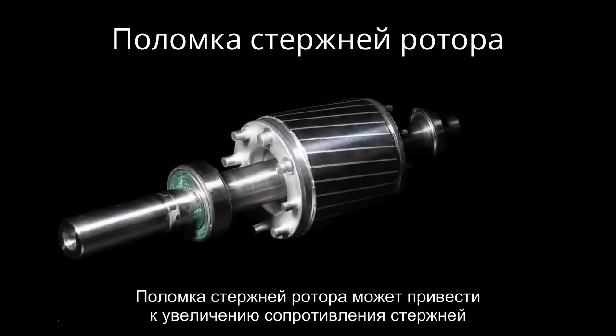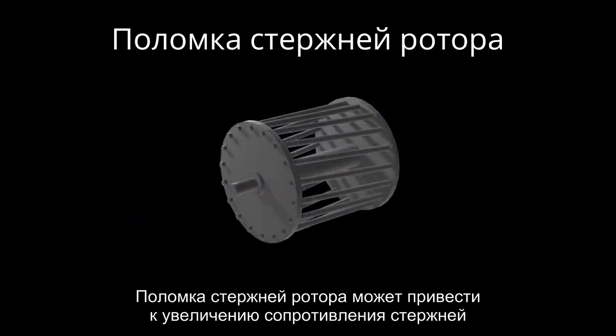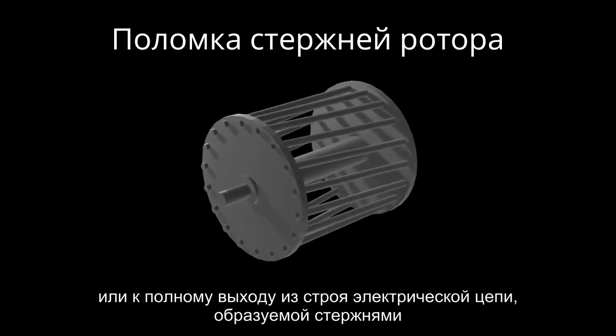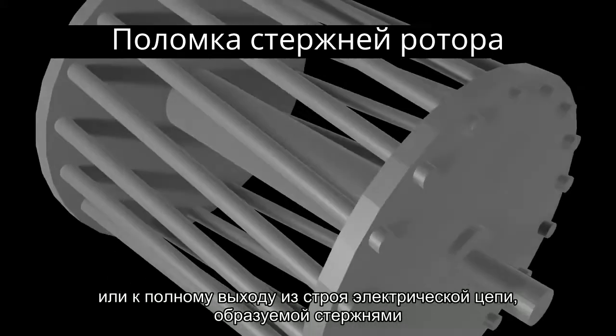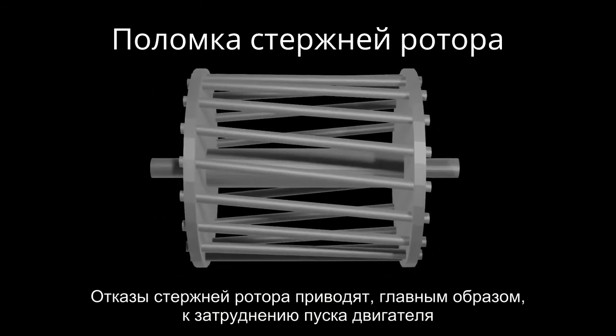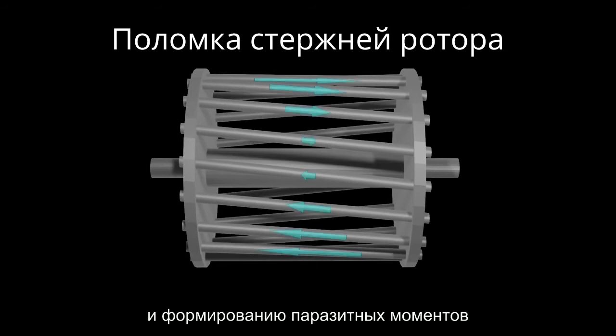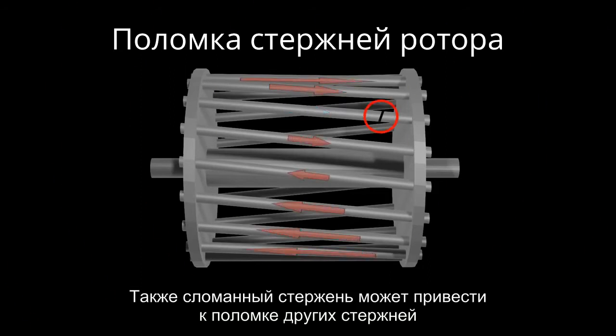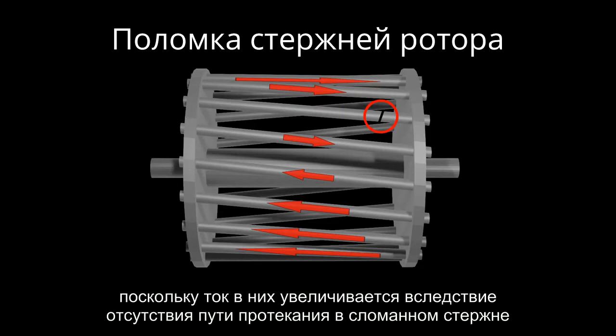In the case of rotor bars, the fault may increase the resistance of the bar or completely break the bar electrical circuit. Rotor bar failures result mainly in engine starting deterioration and generating parasitic moments. Also, the broken bar causes additional faults in other bars because the current in them is greater due to the missing bar current path where one bar is broken.